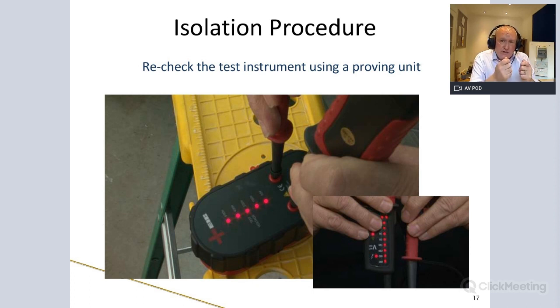It just means your voltage indicator isn't working. That's why we test it again - if we find the voltage indicator isn't working, we have to go back and retest, because it might just be a fault on the proving unit that's gone dead, or it might be the voltage indicator itself. So what you think is now a dead circuit might actually be live.